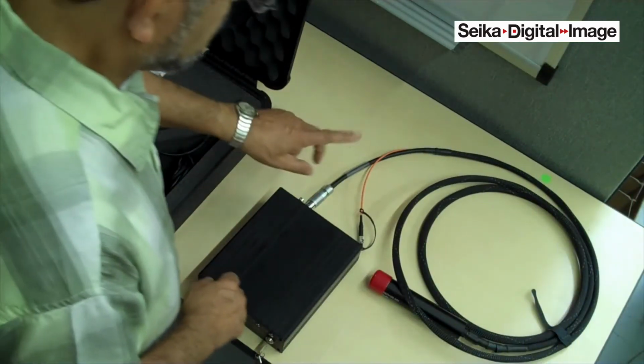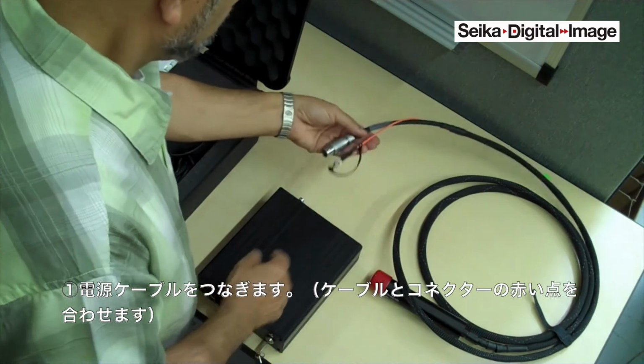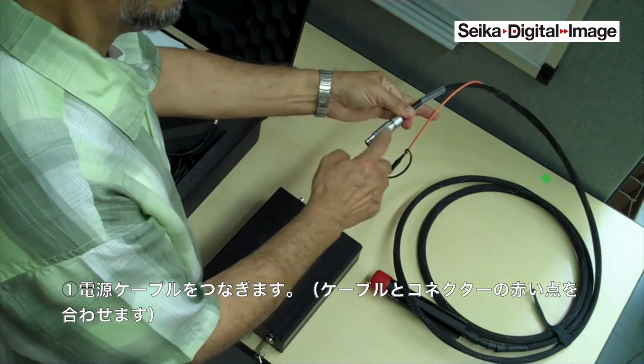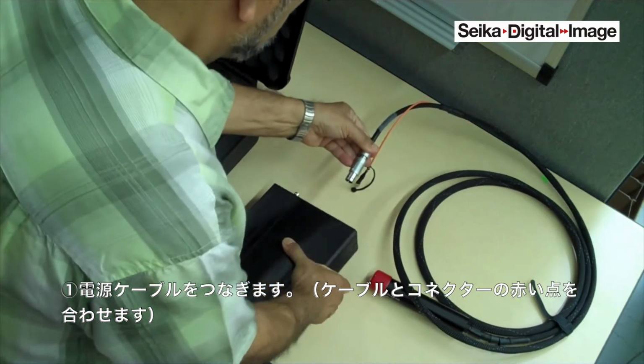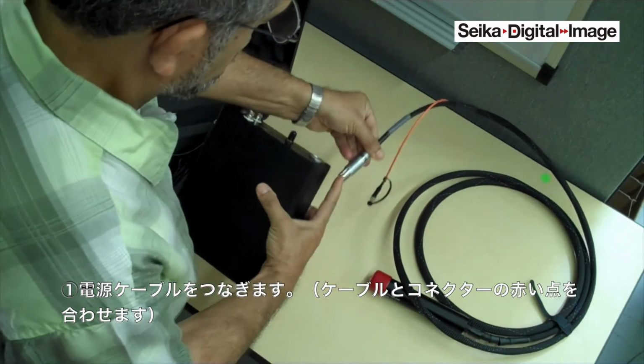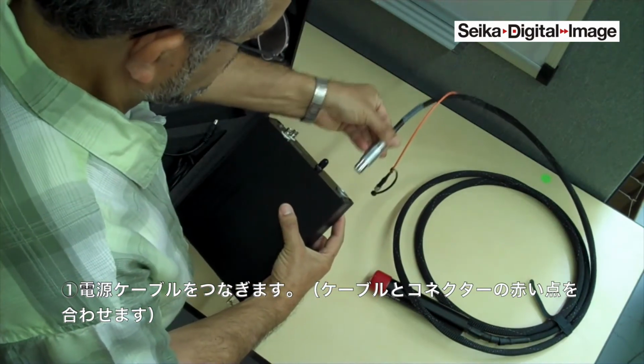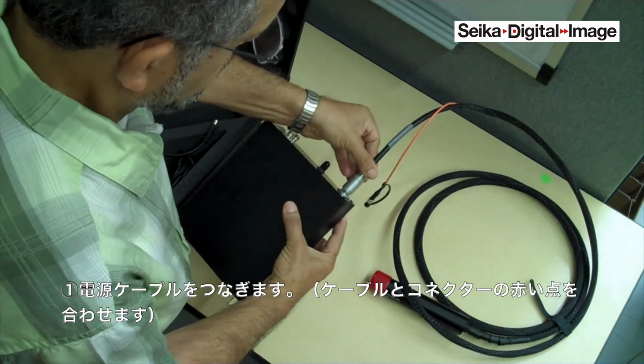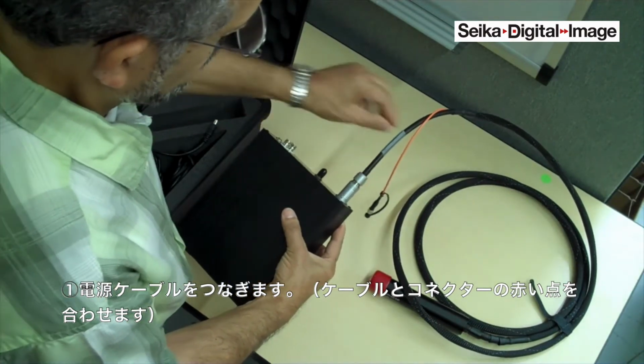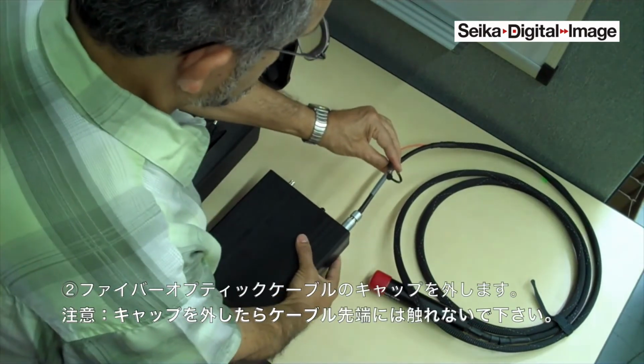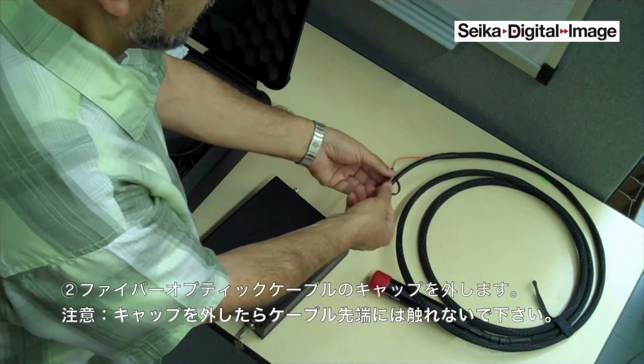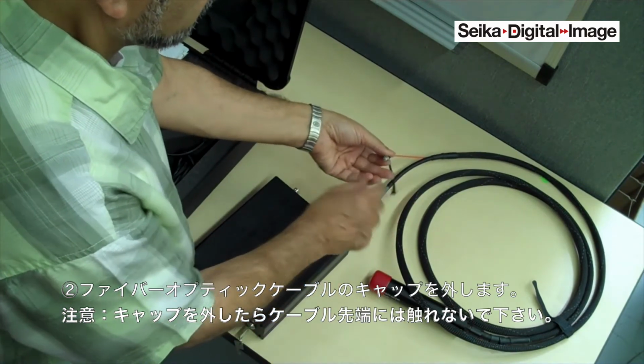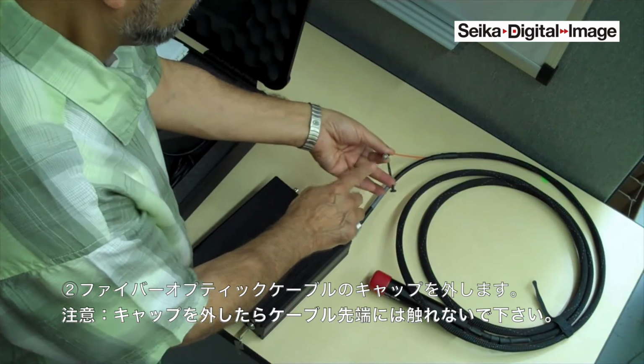So to connect the cable, first you connect the electric connector to the back. There are two red dots, one on the cable, one on the receiver, and you line it up and you lock it in. As far as the fiber optics is concerned, the fiber optics has a cap. Carefully take it out. Make sure you do not touch the end of the fiber.